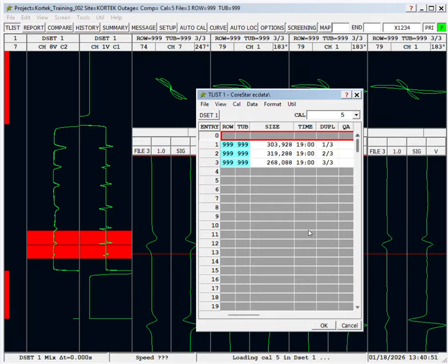Dings are very common, and they can happen from assembly of the heat exchanger, when in the tube mill they're inserting the tubes in through all the tube support plates. Sometimes they have to wiggle them to get them to go through all the different support plates during assembly. So sometimes you get dents or dings that way. And a lot of times you'll see them in pairs, because as they're wiggling the tube back and forth to try to get them through the support plates, you'll get two dents or dings.